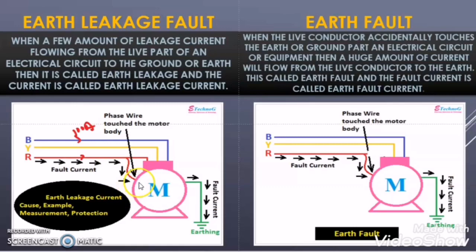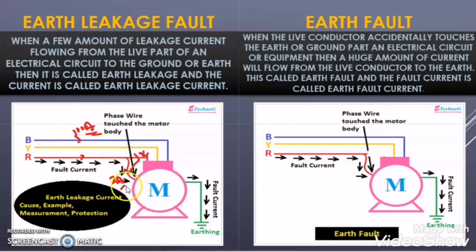But due to something happening, 2 Ampere of current is spilling to the body of the motor. So 2 Ampere of current is leaking to the body of the motor and 98 Ampere of current is flowing through the R phase. But the other two phases — blue and yellow — are having the same current of 100 Ampere each. So this condition is called the earth leakage fault condition. Here you will observe that a very minor amount of the supplied current is flowing through the earth and the maximum current is flowing through the motor.